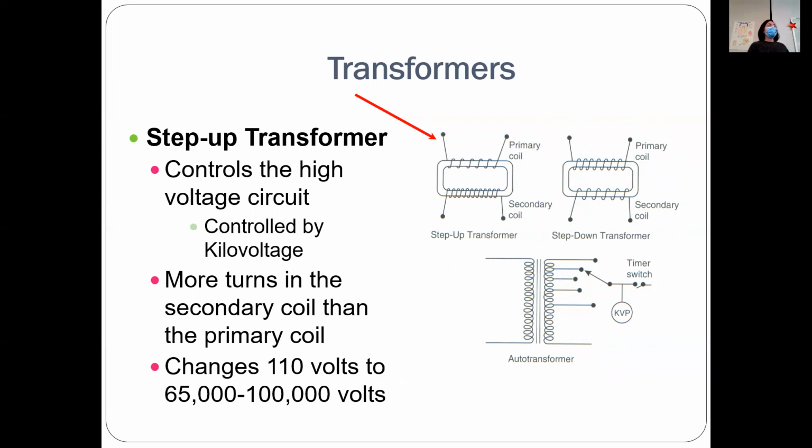It says 65 kVp, 7 mA or something like that. They all have it, and that's all you really have to know. Those two things are what's creating this energy. And so step down is controlled by mA. Step up is controlled by kilovoltage.